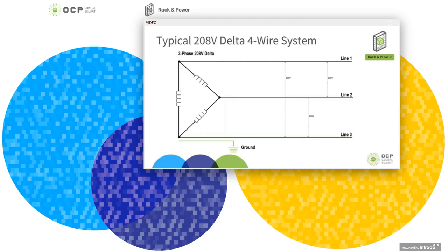So the 50 amp, which is kind of the typical size that we've seen, especially at Microsoft, the 50 amp system will yield about 17.3 kilowatts, but still with best practice derating to about 14 kilowatts. Not quite as high as the 32 amp. And what happens here is you use a lot more copper to achieve that 14 kilowatts.